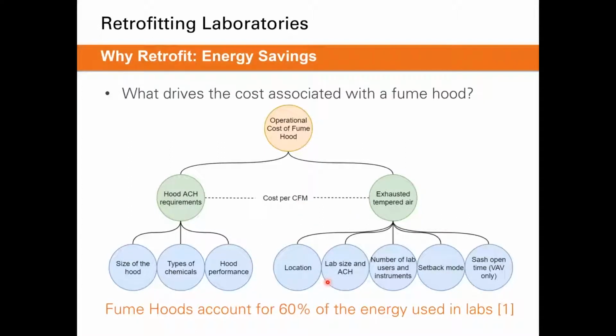The lab size and ACH would determine how much air gets exhausted through the fume hood. Also, the number of lab users and instruments in the space would add to the heat loads in the space and can drive up that number. Whether or not there's an option to go back into a setback mode. So if your lab has just one constant volume for the supply and doesn't have the ability to turn down when the thermal demands are met or when the lab is not occupied, then that would also drive up the amount of exhausted tempered air through that space.